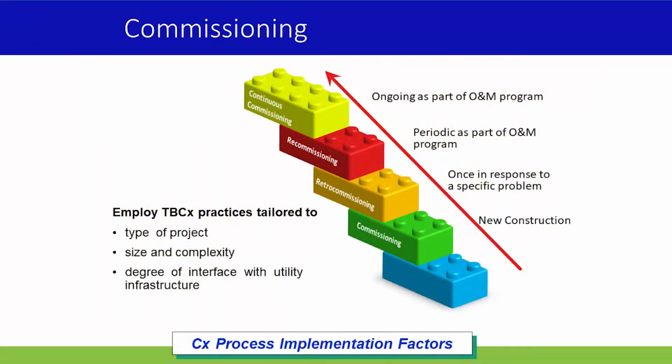Now, what we do here is we do two things. One is the minimally code compliant building, and then we go back and make changes to the model that help us to see how the building is being designed or operated, which then goes back and sees what the savings are. Now we talked about commissioning, so let's take a look at the commissioning itself.